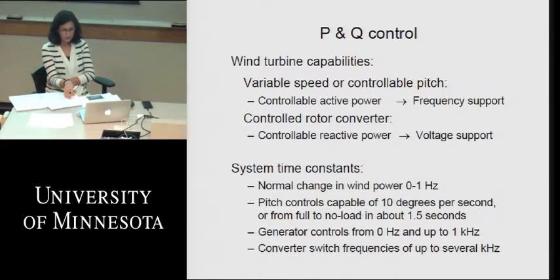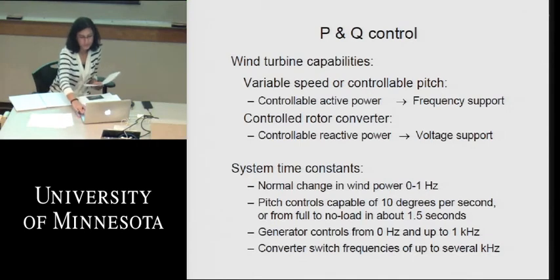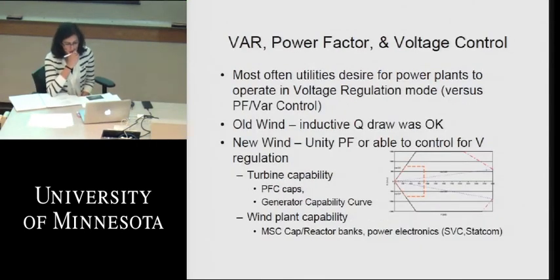So VAR control, power factor control, and voltage control are all kind of names for not the same thing, but these three affect each other. When you change the VARs in and out of the turbine, you're actually affecting its power factor, and you're also affecting voltage changes out where the generator connects to the outside grid. So most often the utilities desire the power plants to operate in a voltage regulation mode instead of a power factor or a VAR control mode. And that's to make them analogous, or to emulate the same kind of operation a standard conventional synchronous unit would.